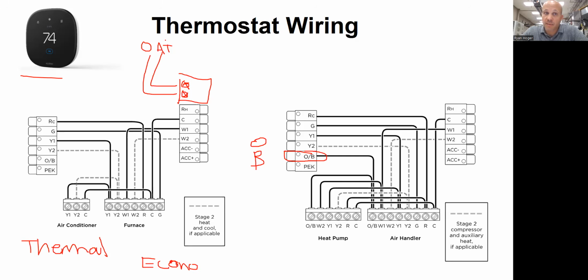What does that mean? That means it has a way to know the outdoor air temperature, and it has a programmable set in there that you could say, hey, at this outdoor air temperature, flip me. You don't need a dual fuel thermostat if you are going to have a single fuel, i.e. all electric. So a heat pump with electric resistance heat needs a regular heat pump stat. And a dual fuel one, which is any kind of heat pump with anything other than electric resistance heat, needs a dual fuel heat pump thermostat.